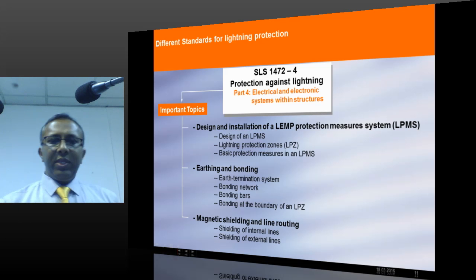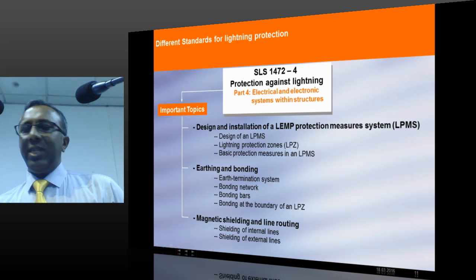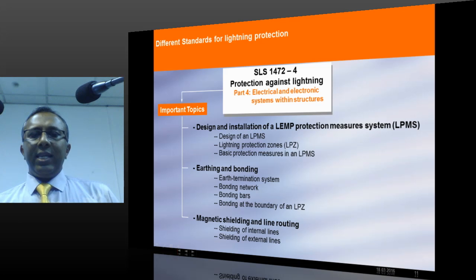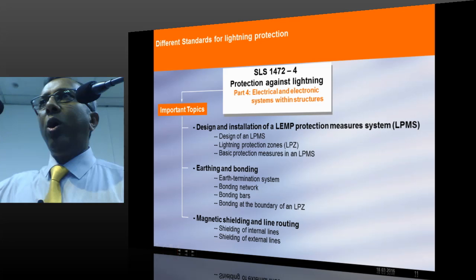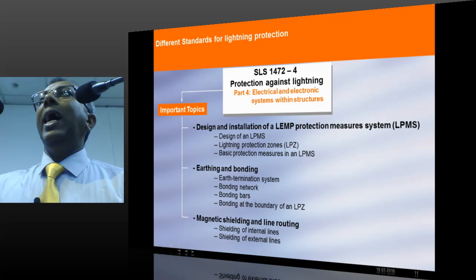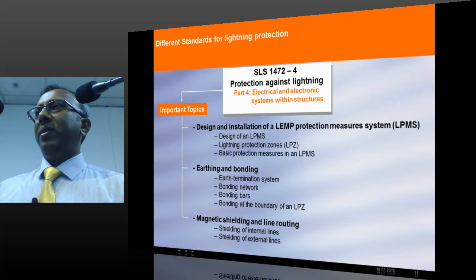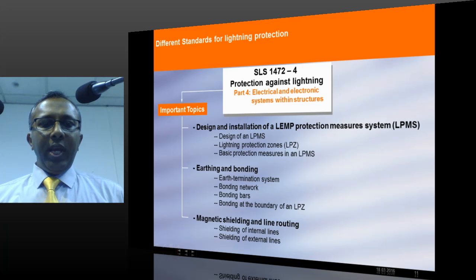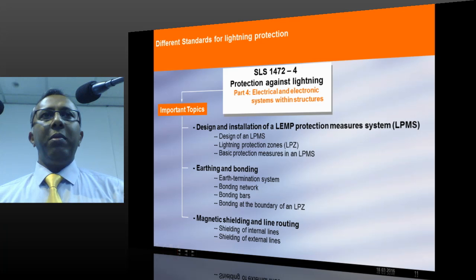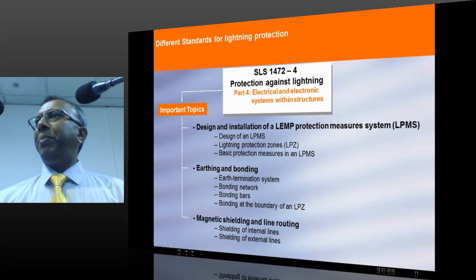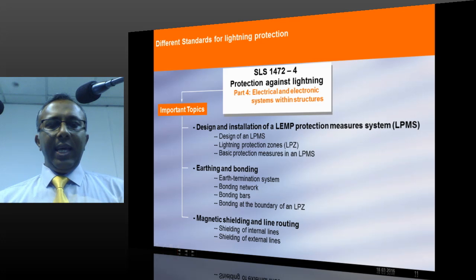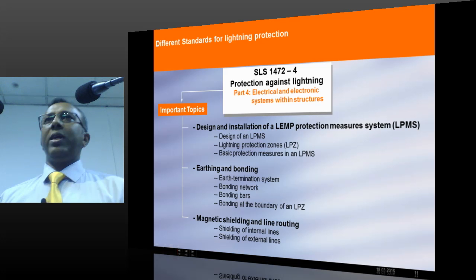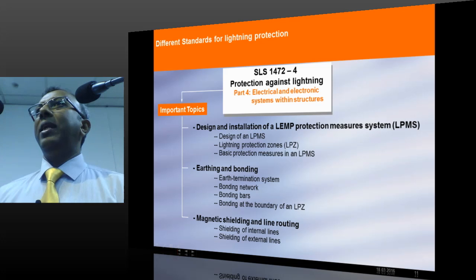Design of LPMS, lightning protection zones, basic protection measures in LPMS, and the second part talks about earthing and bonding. Please understand, earthing is not the only subject. Earthing and bonding: earth termination, bonding network, bonding bars, and bonding at different boundaries in an LPZ are explained. Then magnetic shielding and line routing. What kind of magnetic couplings can happen during a lightning strike? How you have to route the cables is also explained.